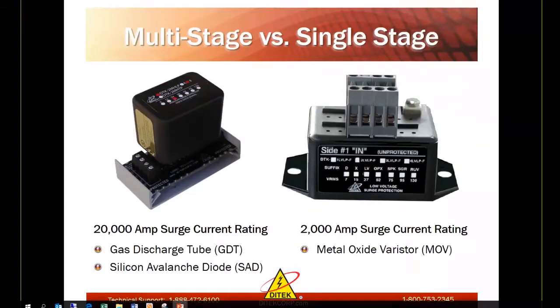Multi-stage versus single stage. The modular device that we spoke on is the F or the B series. It's a two-pair device, and you can see that we offer it in multiple voltages. It has a 20,000 amp surge current rating, the highest surge current rating available for a modular type of low-volt surge protector. The components within that device are a gas discharge tube to dissipate some of the energy, and then the SAD, silicon avalanche diode, to take that surge to ground.